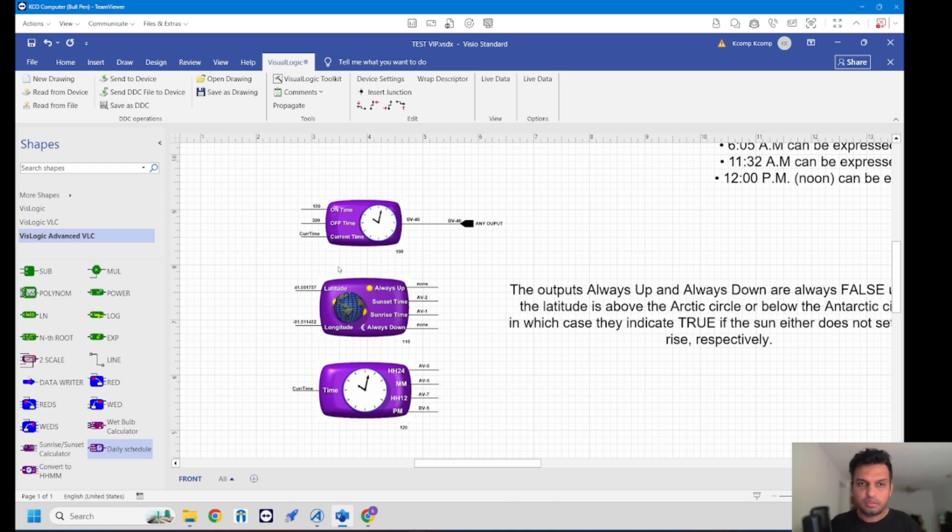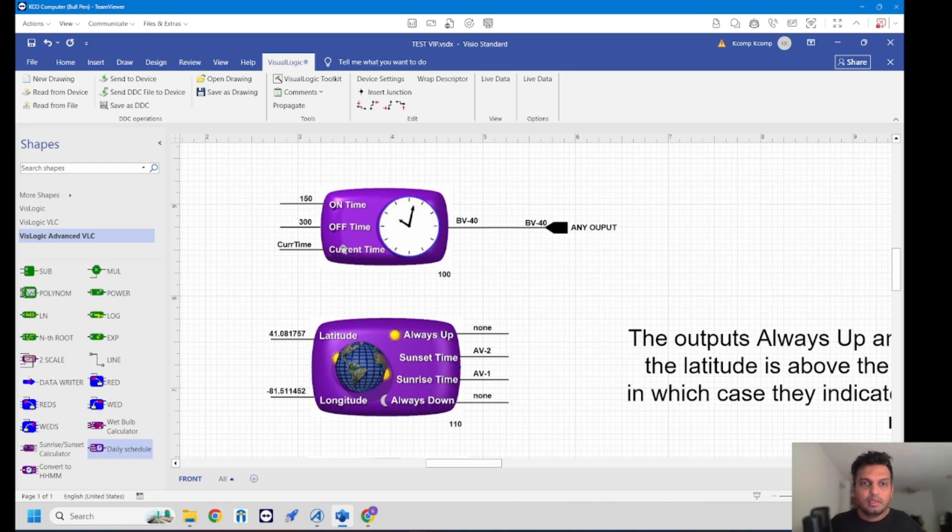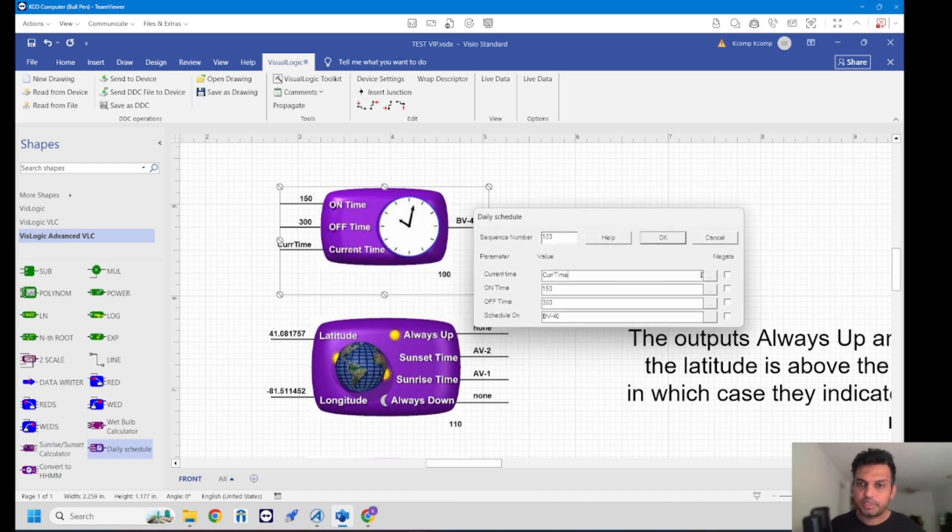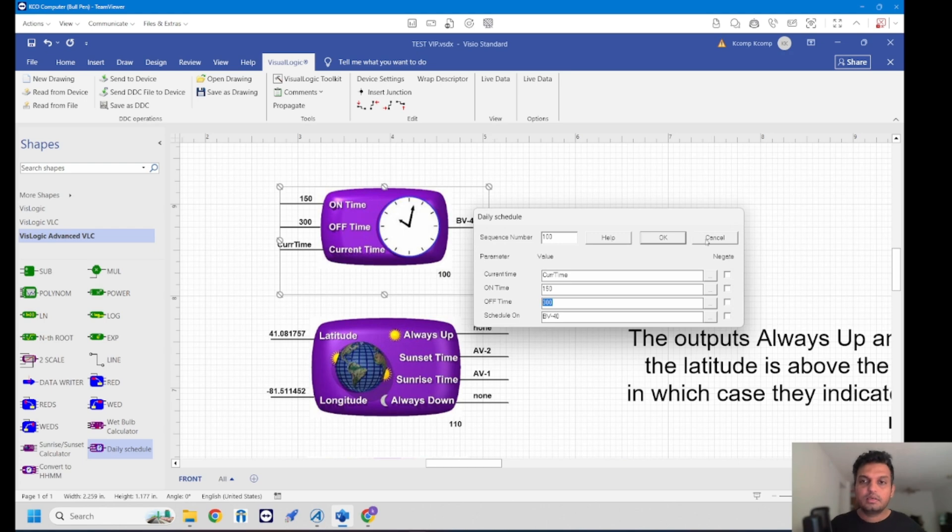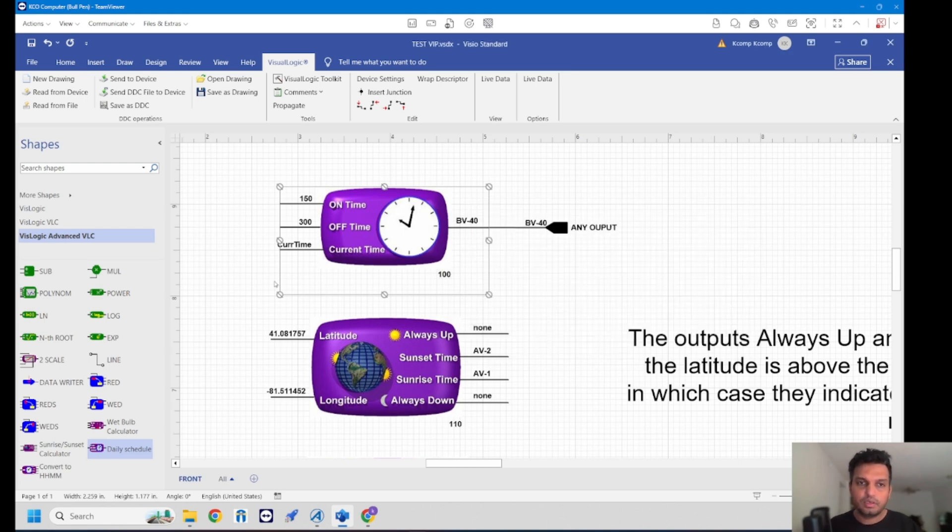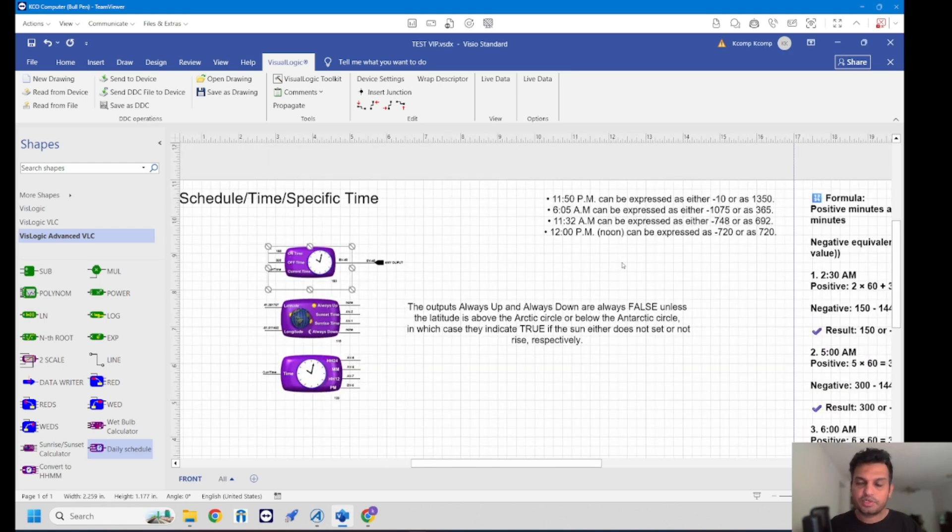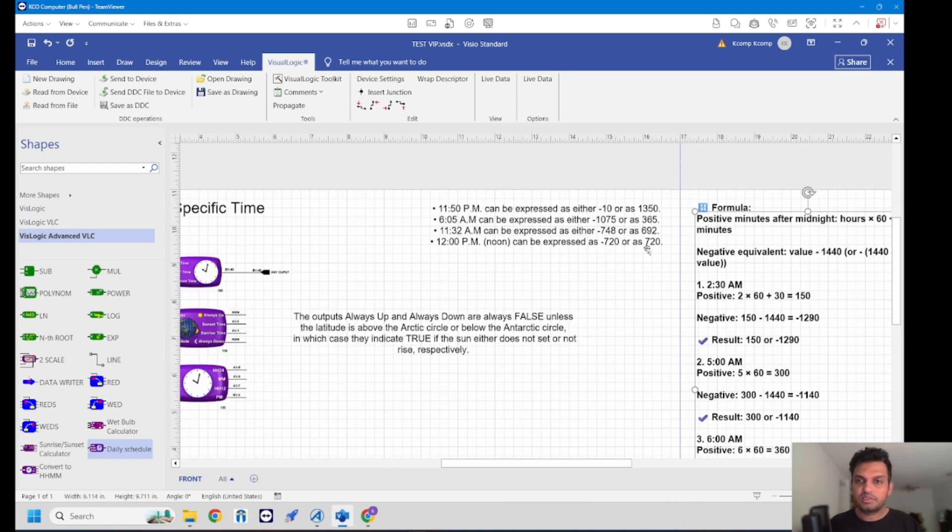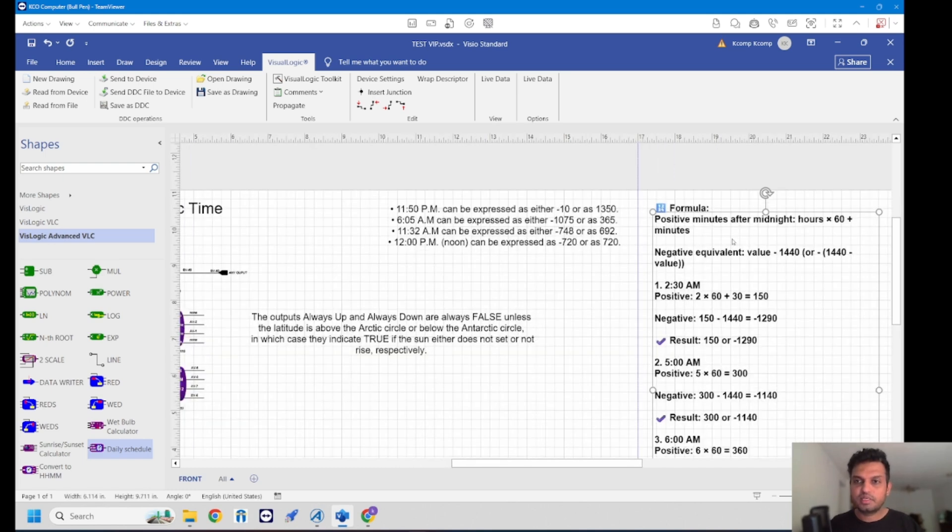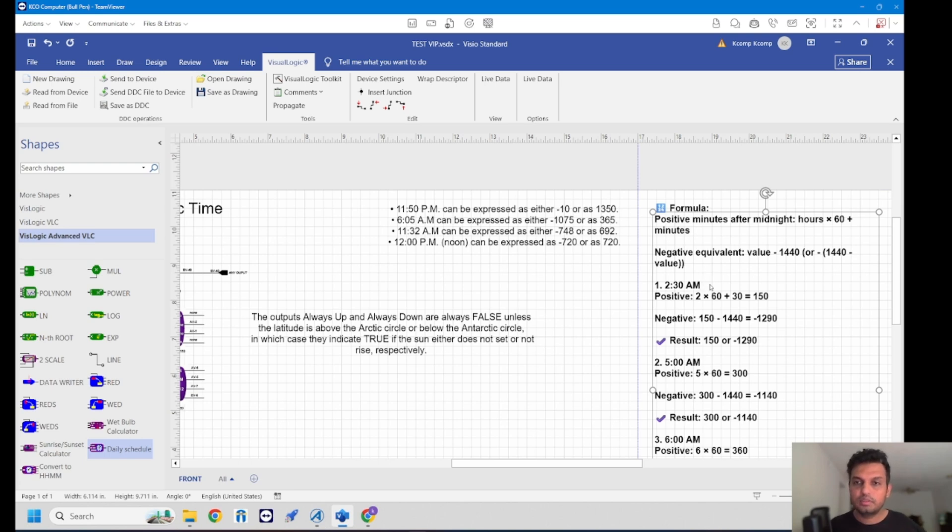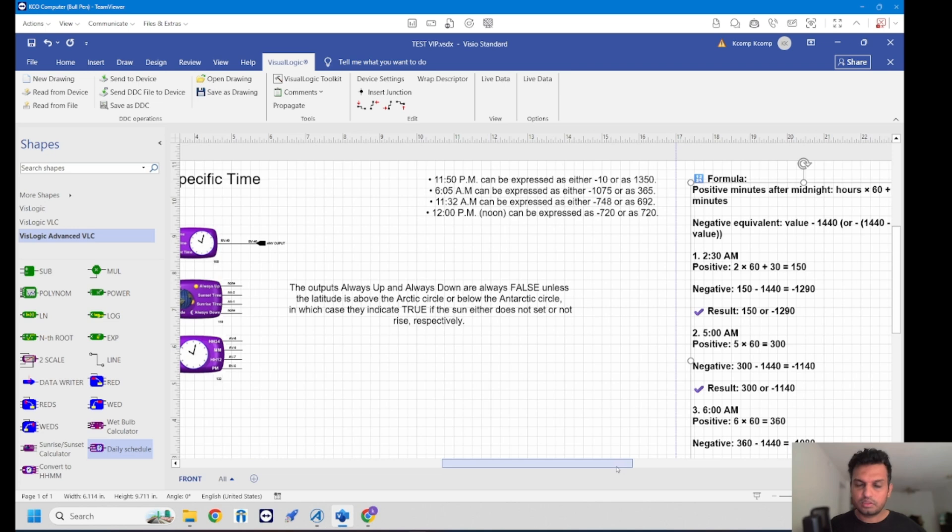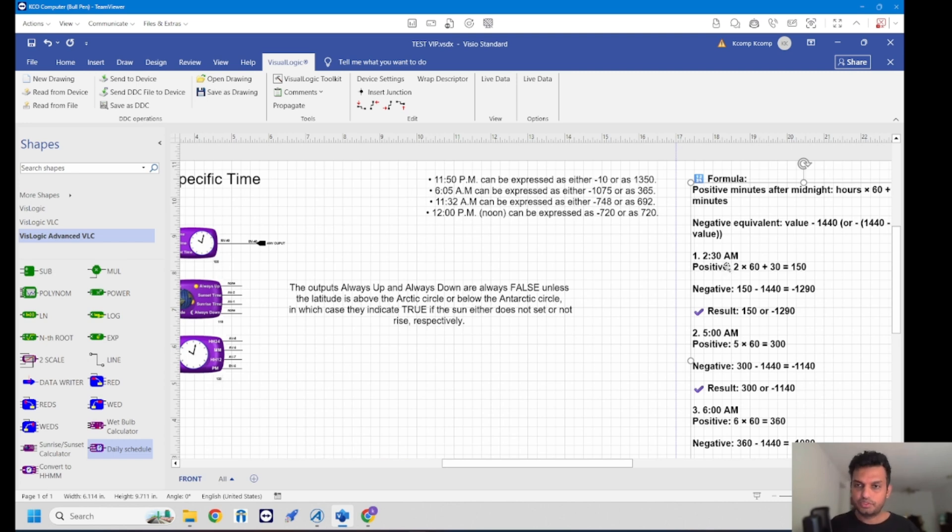This gives me time to turn on or off. In this function block there's on time, off time, and current time. Under the current time when I double click I'm making sure that the current time of the device is read. There's an on and off time. How are these values calculated? Allerton uses an expression which is a negative expression or a positive expression. The formula is here. After midnight if you want to do a positive minutes or an hour you could be doing it with the conversion as mentioned here. If it's a negative conversion you would be using a constant of 1440.